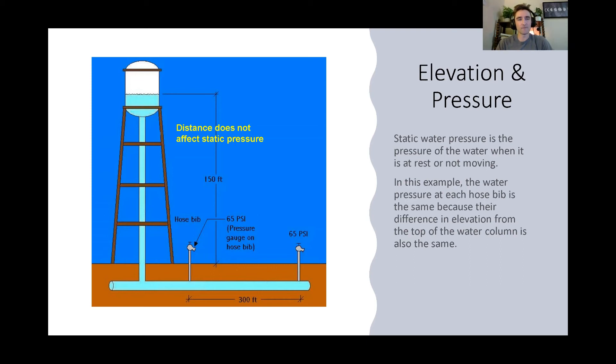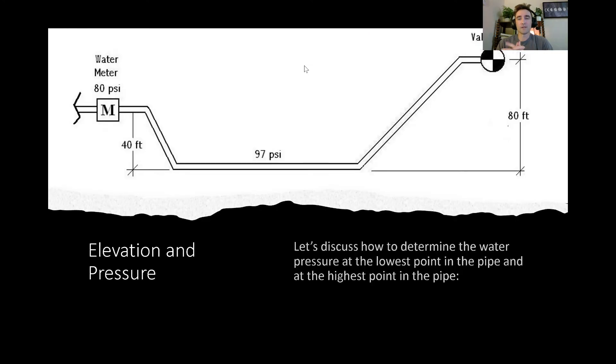So in this example, let's take a look at the drawing of the water tank. It's 150 feet to ground level. And we know at the hose bib, we have a pressure of 65 psi. And if it's really close to the water tank, it will be 65 psi. If we move 300 feet downstream, but the elevation stays the same, then it will be 65 psi. Exactly the same. So let's discuss how to determine the water pressure at the lowest point in the pipe and at the highest point in the pipe.